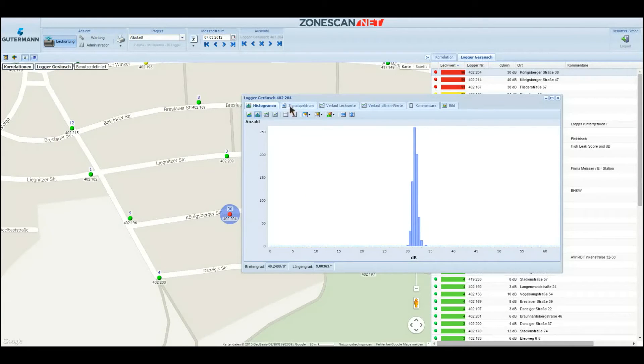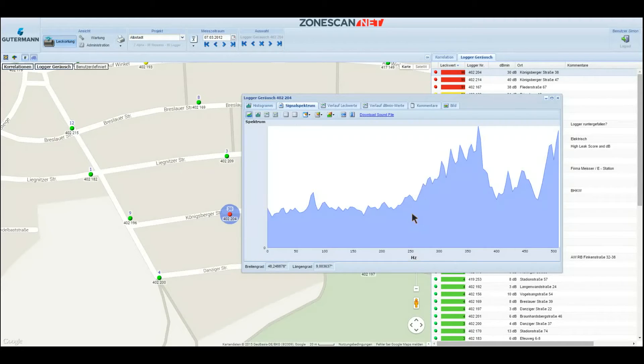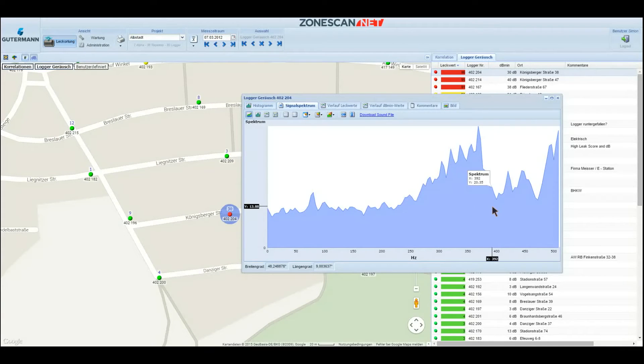To differentiate between all possible sources, you can take a closer look at the spectrum in the next window. A leak is usually at the upper end of the spectrum, as visualized very well in this case. The peak is in a high frequency range, typical of a leak noise in harder materials as opposed to softer ones.